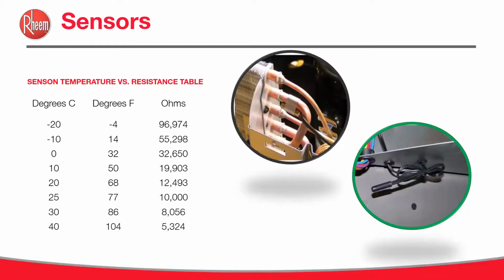So as I said, these sensors are negative temperature coefficient type thermistors, which means the resistance lowers as the temperature increases. So as you see here at -10, let's pick for instance, that's 55,000 approximately. If you go to -20, now the resistance is 96,000 ohms. You need to have a good multimeter. If a technician goes, they need to have a good meter to read it. Thing to remember is these sensors have 4.5 to 5 volts DC sent to them. So if the sensor checks out, you're going to want to make sure that you have that voltage present. And again, that's DC voltage, not AC.